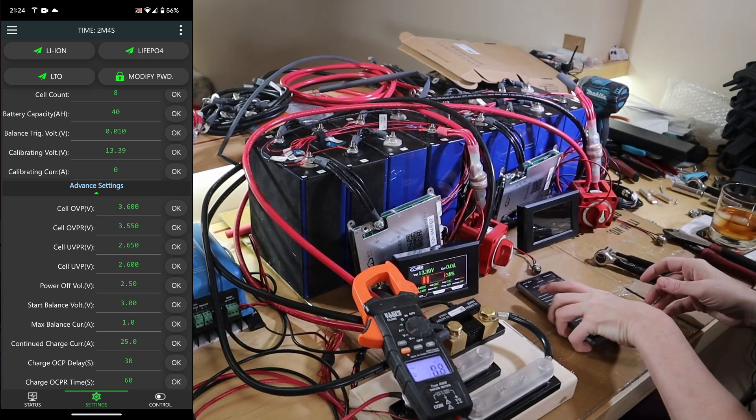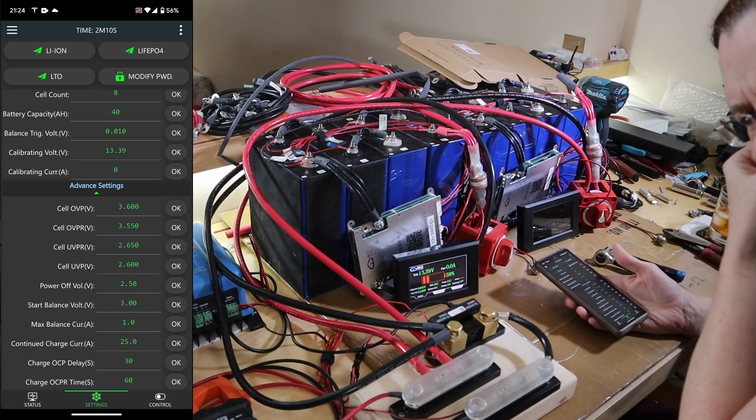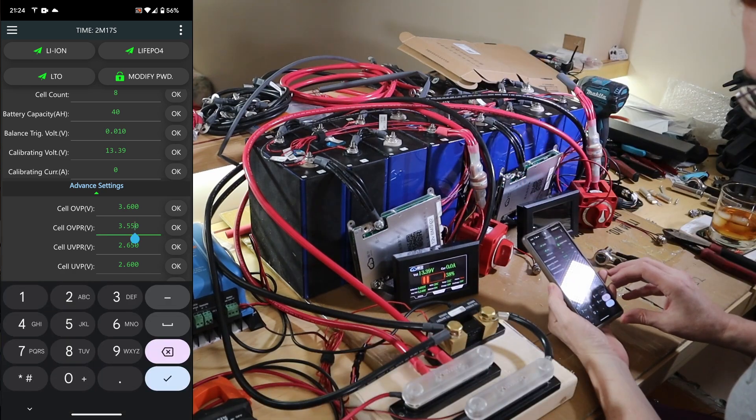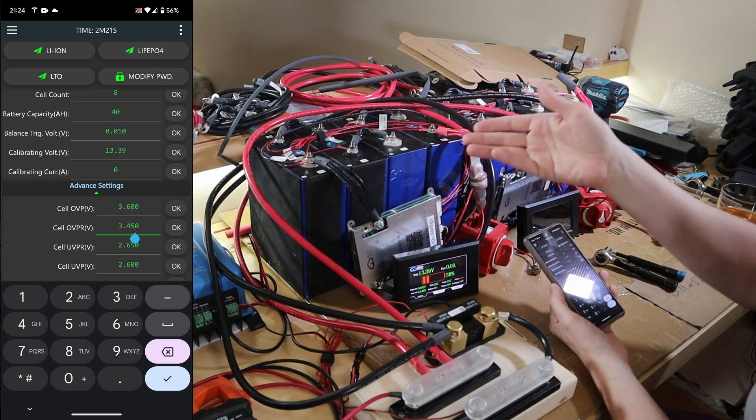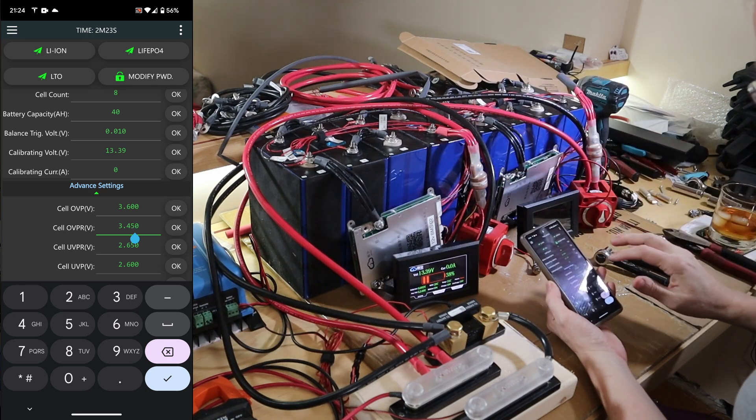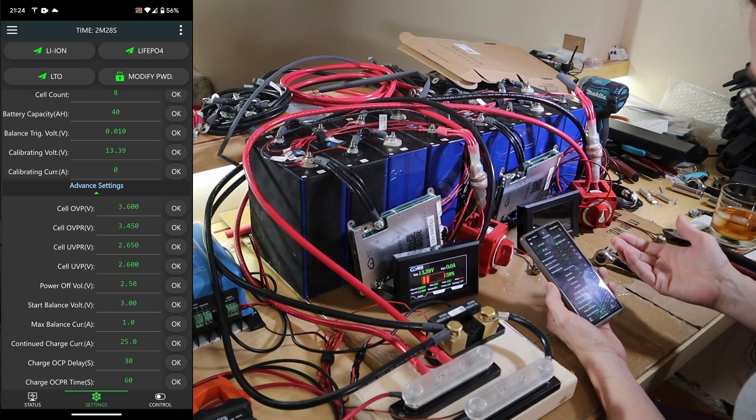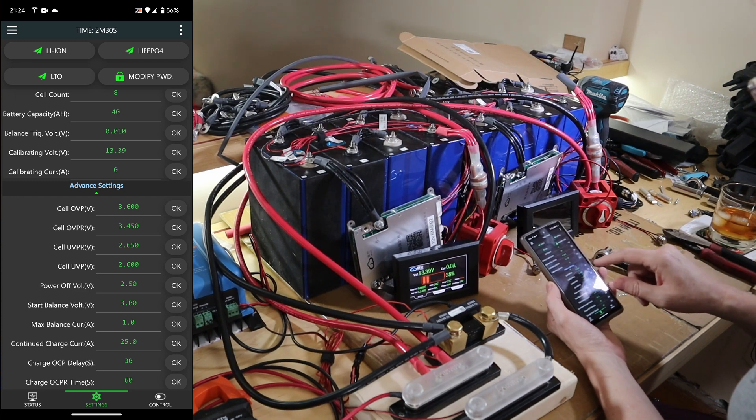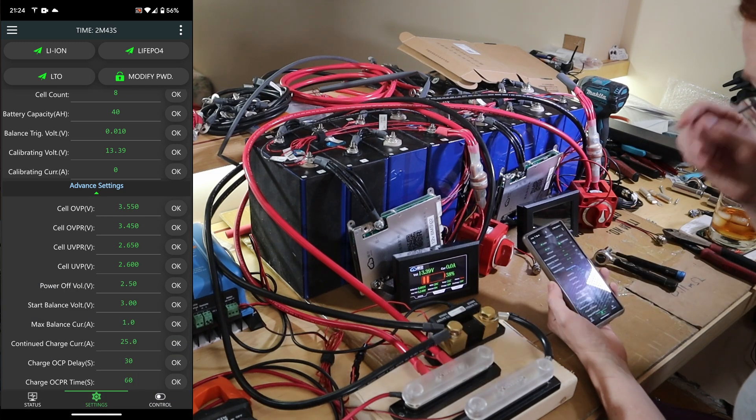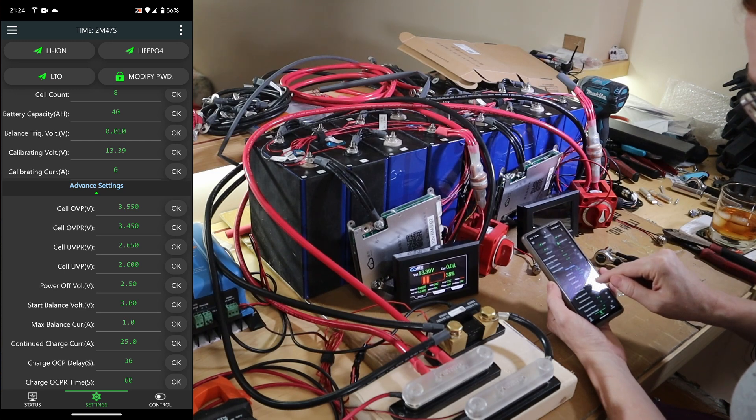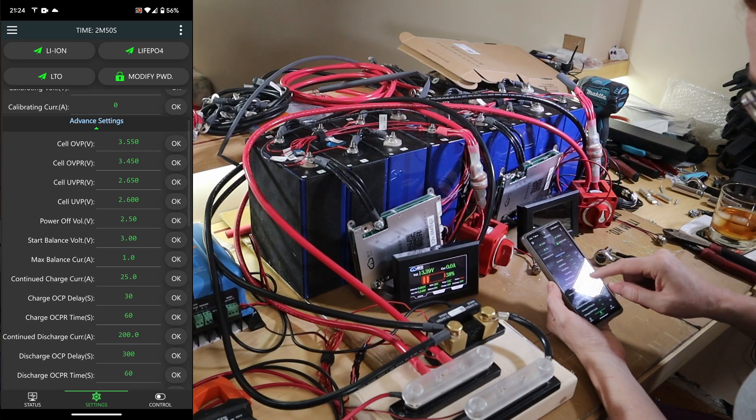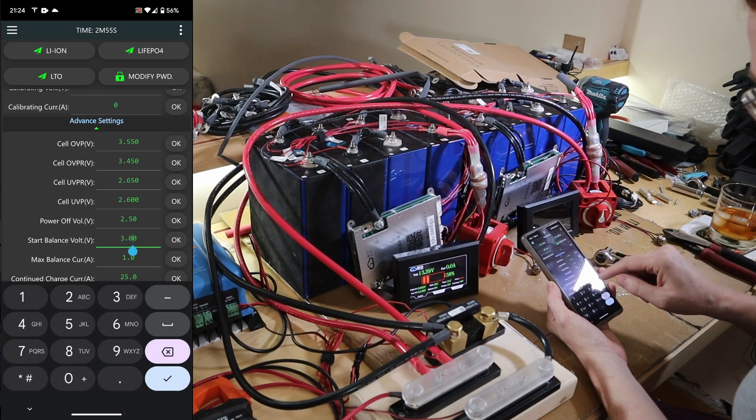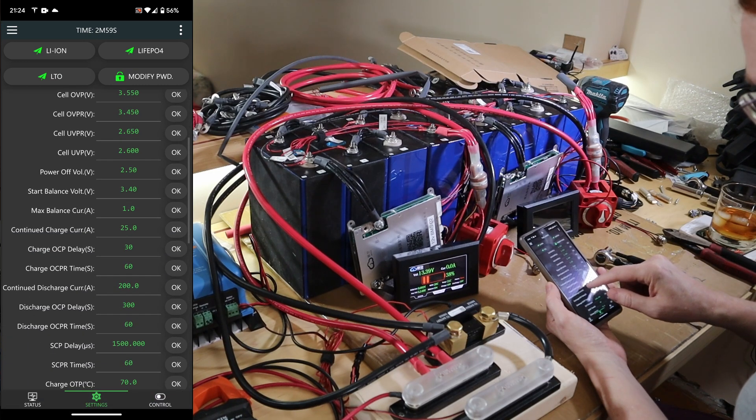It obviously defaulted to something else. It's seeing the temperature. I think we set the over voltage protection to 3.55. I'm not doing a capacity test on these because these are from the first 48 volt and I've already capacity tested them. Under voltage protection is set to 2.65. Over voltage return is 3.45. Under voltage protection is 2.6. Set that to 2.65 for recovery. Power off voltage is 2.5. That's fine.